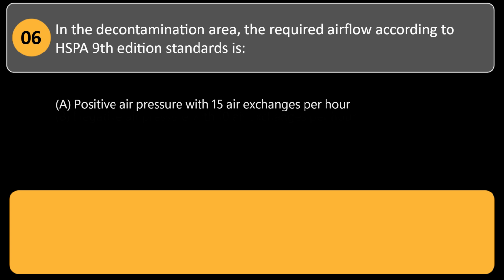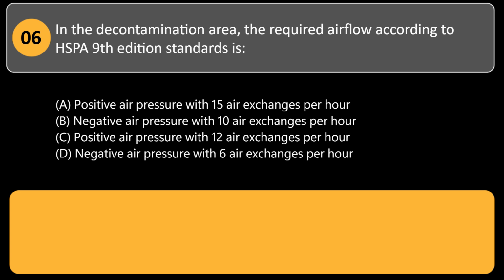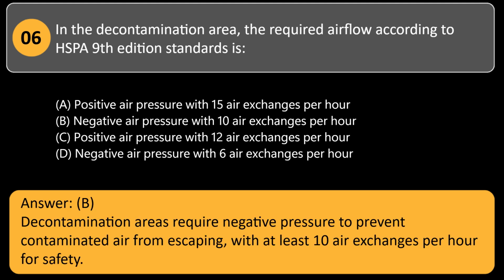In the decontamination area, the required airflow according to HSPA 9th edition standards is A. Positive air pressure with 15 air exchanges per hour. B. Negative air pressure with 10 air exchanges per hour. C. Positive air pressure with 12 air exchanges per hour. D. Negative air pressure with 6 air exchanges per hour. Answer: B.